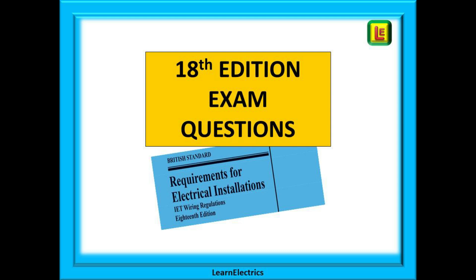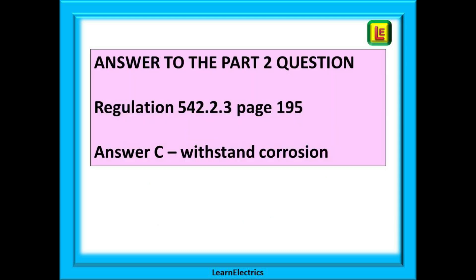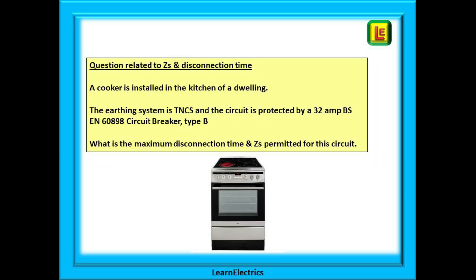Let's look at some exam-type questions. But first, the answer to the foundation earth electrode question from the last video, part 2 of the 18th edition training: the answer is found in regulation 542.2.3 on page 195, and the answer is C — the electrode shall be selected to withstand corrosion. Now back to ZS. A cooker is installed in the kitchen of a dwelling. The earthing system is TNCS and the circuit is protected by a 32 amp BS EN 60898 circuit breaker type B. What is the maximum permitted disconnection time and the maximum permitted ZS for this circuit?